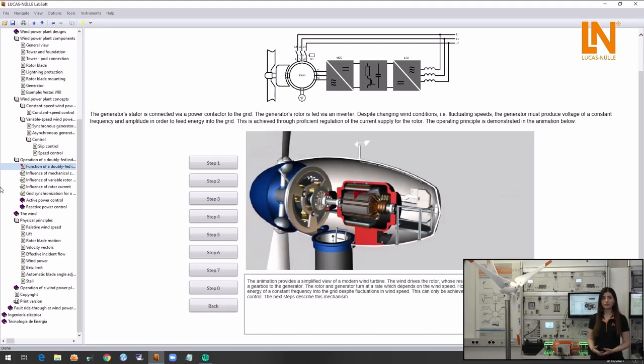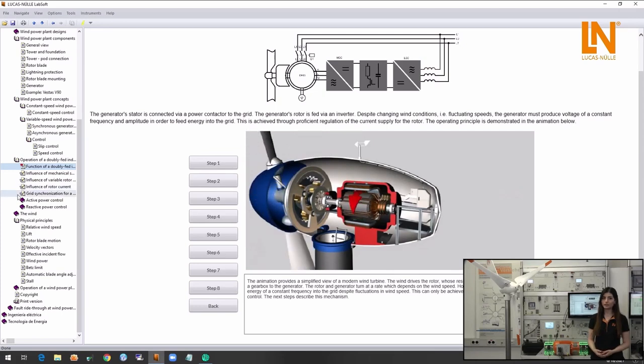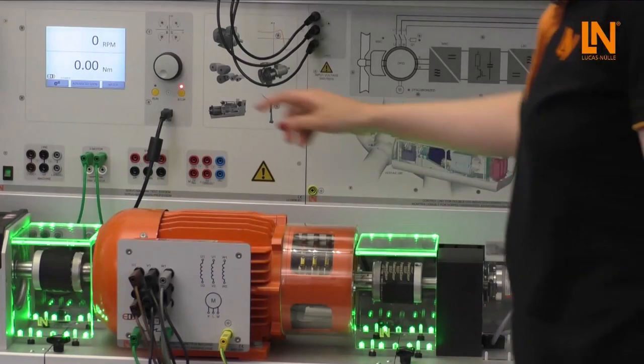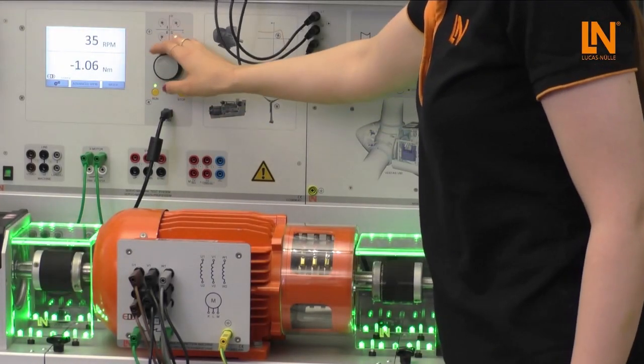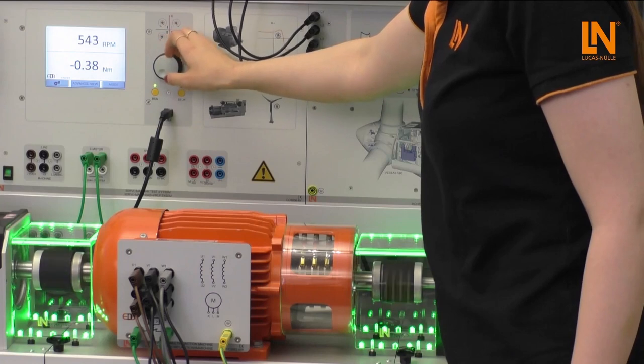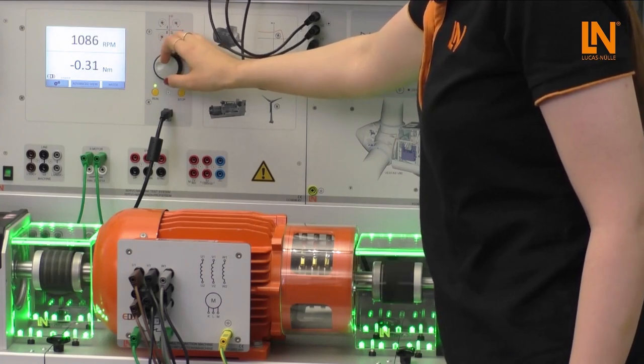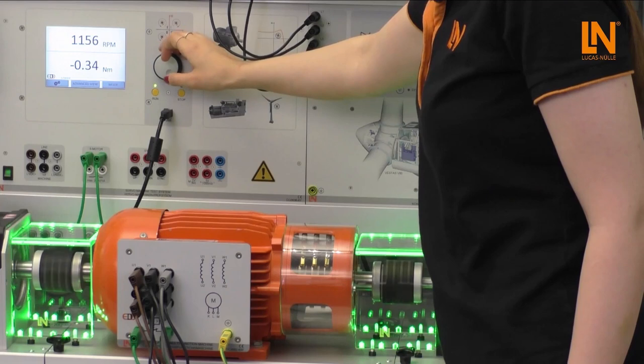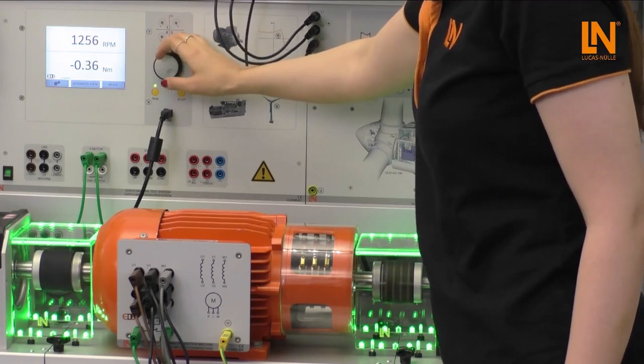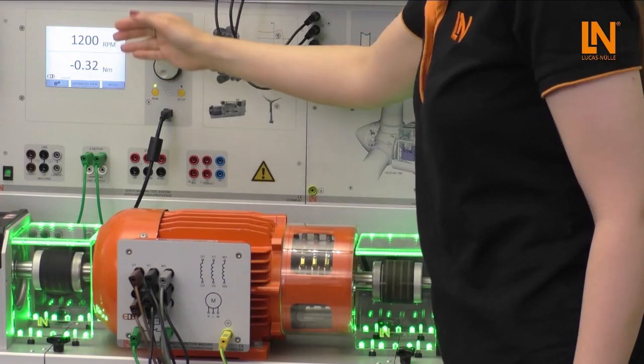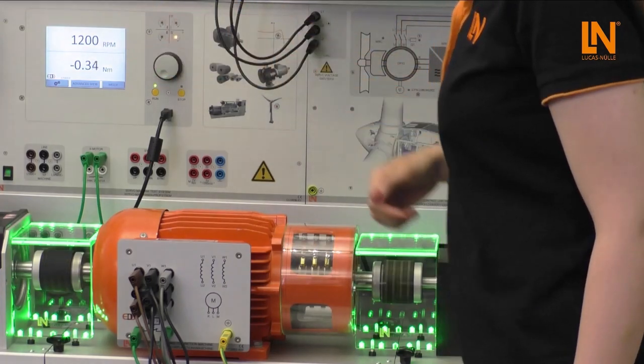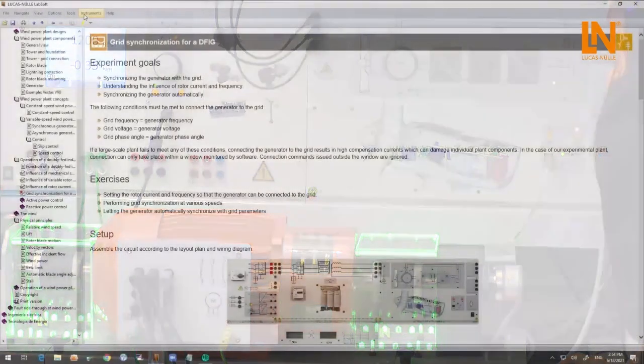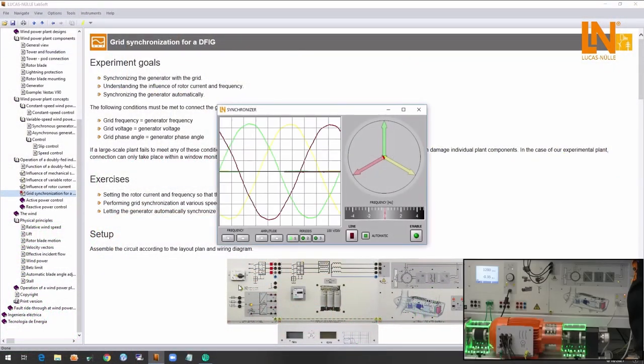As the first experiment I would like to show you the manual synchronization process of the wind power plant to the grid. I'm going to start the servomachine test system and give it a speed of around 1200 rpm. This replicates the wind speed. Now I'm going to open the instrument synchronizer in Labsoft.